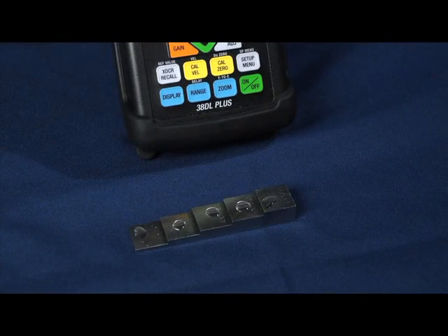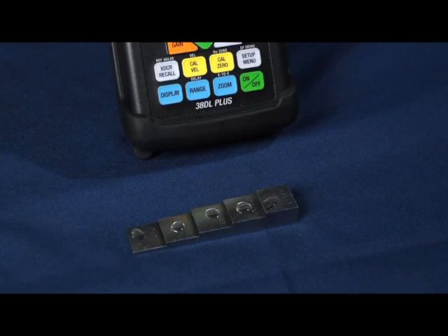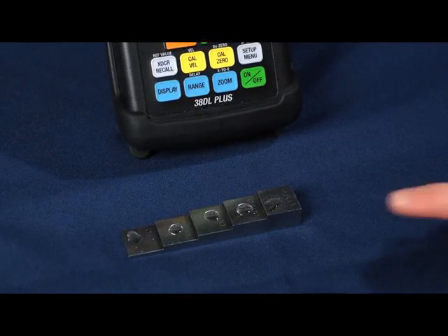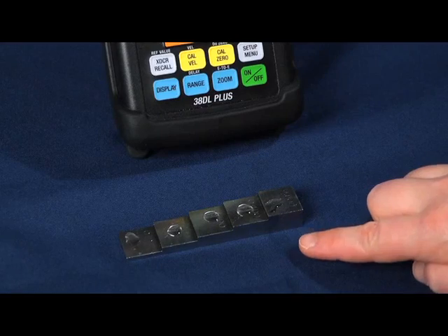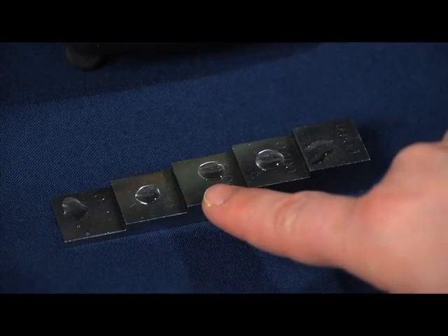At this point, we are ready to perform a two-point calibration. In this example, we are going to be calibrating to a five-step carbon steel test block where the maximum thickness is five hundred thousandths and the minimum thickness is a hundred thousandths, with a hundred thousandths steps in between.